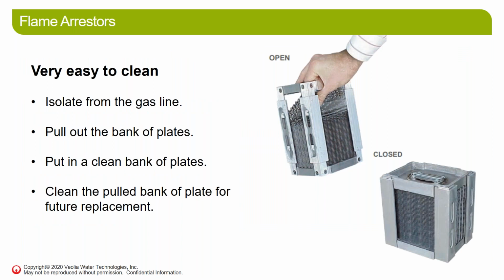Typically we provide these systems with two PRVs, so you can isolate one, open up the flame arrester, clean it, and pull out that bank of plates and clean them out. They're usually aluminum, so you can't use a caustic cleaning solution. Typically you use just water or some kind of light cleaning solution, but be careful, as there's a recommendation in the manufacturer's instructions of what type of cleaning solutions to use. You cannot use caustic, because if they're aluminum, those things will be damaged by the caustic.